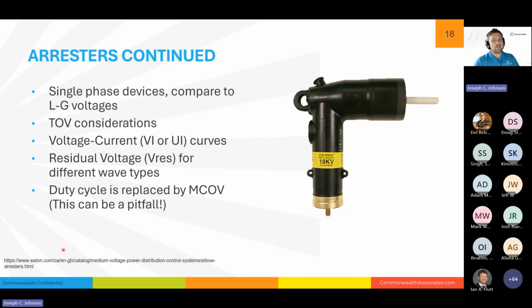And one important note is a lot of times you'll see a duty cycle come up if you're working on speccing these pieces of equipment, even to the point of you'll see something that's a 24.4 kV MCOV, but a 30 kV duty cycle. Even the part number will have -30 in it because it's the old way of doing things. Duty cycle has been replaced by MCOV, and it's a potential pitfall if you think you're speccing something at 24.4 kV MCOV and you order the duty cycle, that's going to be too small. Whereas vice versa, if you think you're speccing the duty cycle and you pick an MCOV of that value, it could be too large. It's really important to pay attention to the differences between those. I have seen that a few times where those have been selected incorrectly.